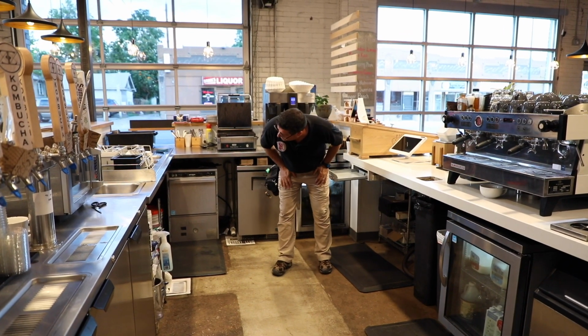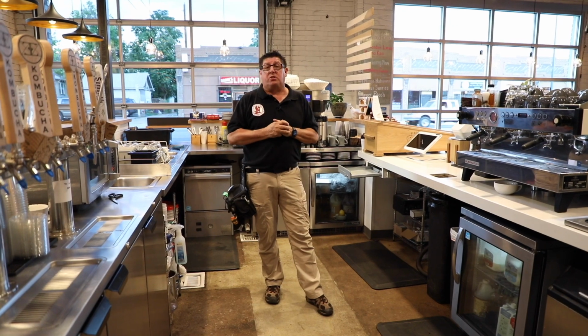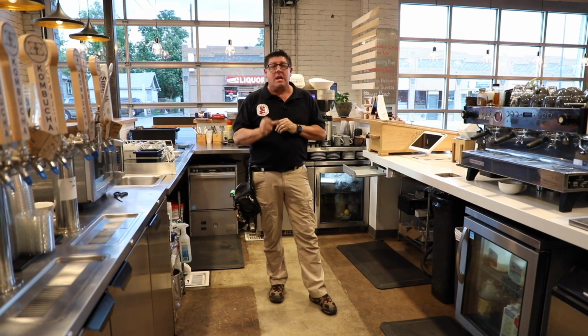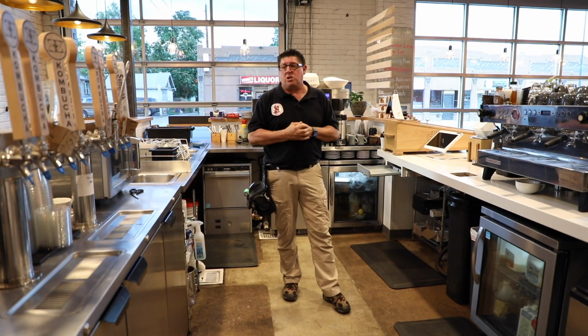I see a lot of outlets that are labeled, and so when I go look in the main electric panel, I'm going to look to see if I have labels in the electric panel. If I don't have labeled ground faulting in the electric panel, then that would be a suggestion I'm going to make to my clients.